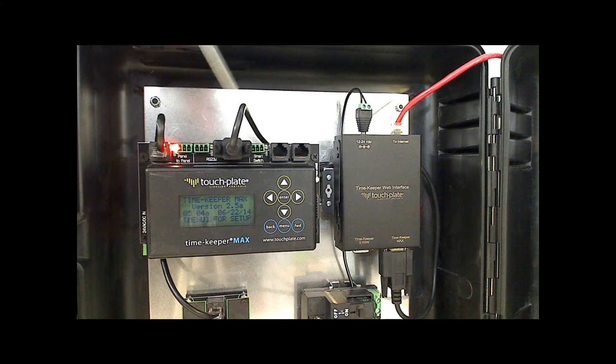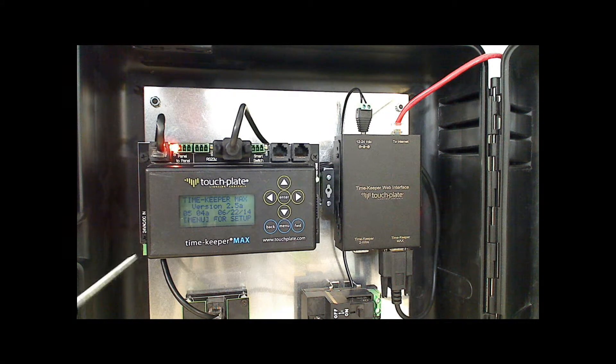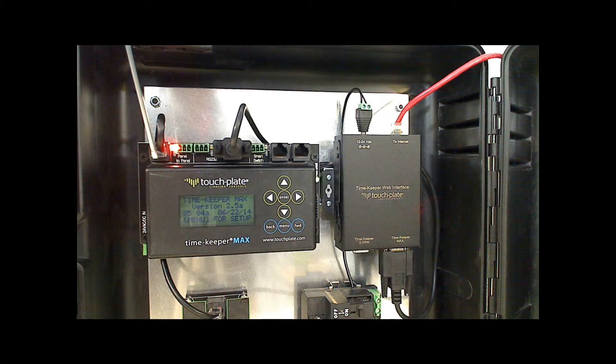There are seven terminations at the top of the Timekeeper and one at the bottom. The first two positions are for the panel-to-panel RJ-45 network. The first RJ-45 takes the standard Cat5 patch cable and passes both power and communication through. The second position uses the 3-position male-to-female connector: terminal 1 is for the ground or shield, terminal 2 is for the minus, and terminal 3 is for the plus.